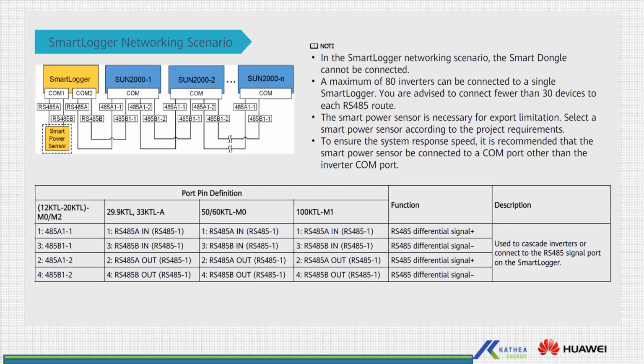If you are to daisy chain your inverters, as I've said, the SmartLogger can take up to 80 inverters. If you are daisy chaining your inverters with a SmartLogger, your daisy chain per COM port is limited to 30 devices on each RS485 route. When you are daisy chaining, the furthest inverter from the SmartLogger, which we represent as N, is connected on out. That inverter's communication goes out to the in of the next inverter, and out of that inverter to the in of the next, up until your closest inverter to the logger. All the daisy chain comes to the in of that inverter, and then you go out of the inverter next to the logger to your COM port on the logger.